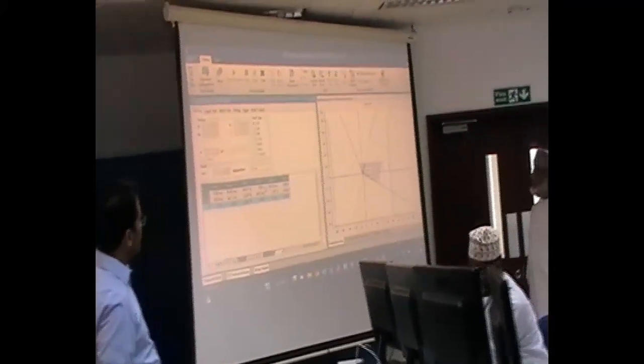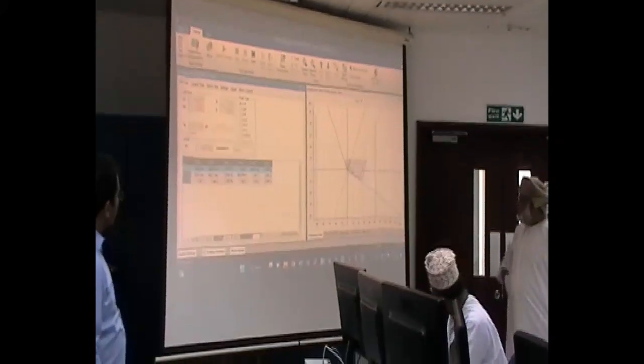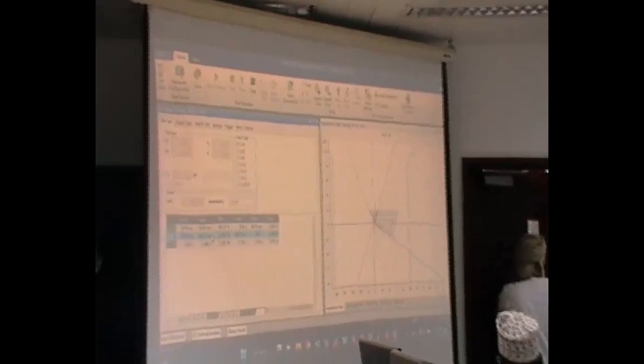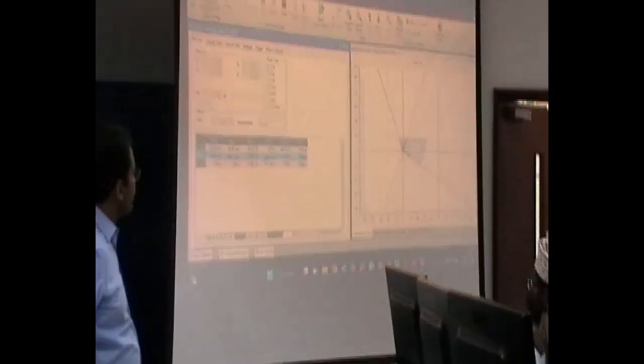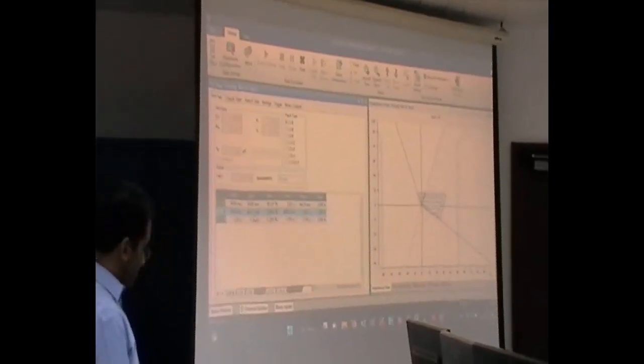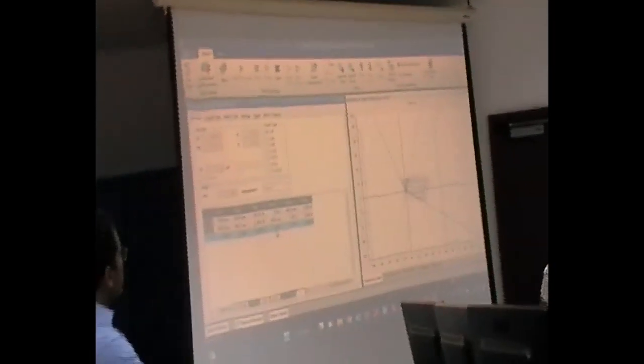So, to conclude this test, assuming the setting is 0 seconds for zone 1, we've got 58 milliseconds. Zone 2, assuming it's supposed to be 400 milliseconds, it got 442 milliseconds. And zone 3, 1.246 seconds, and it was supposed to be 1.2, basically. 1.246.